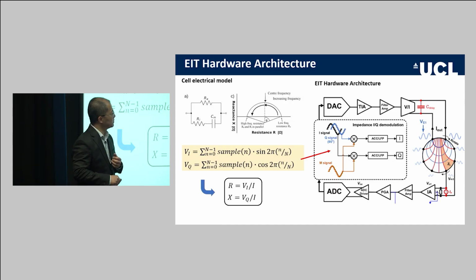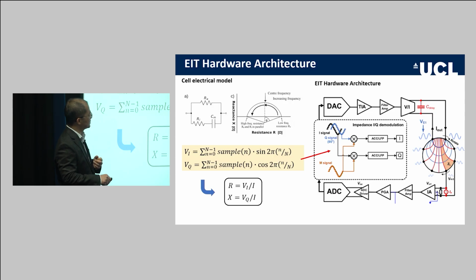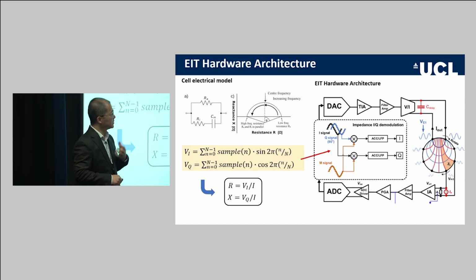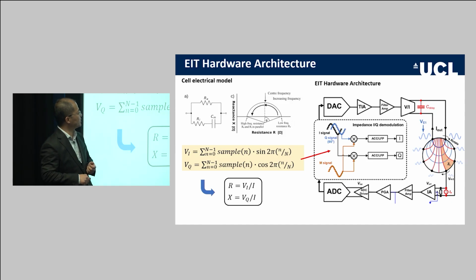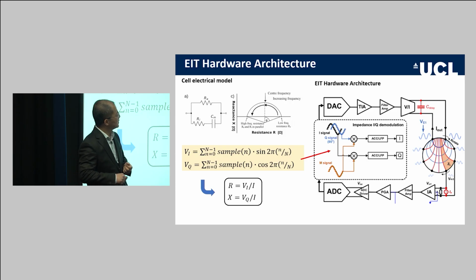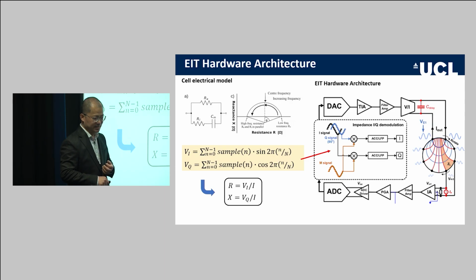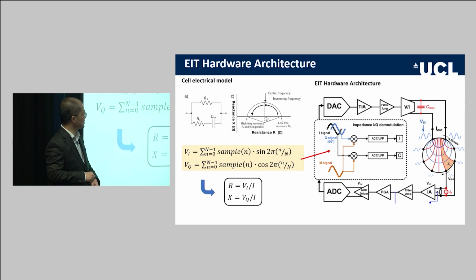So this is a traditional hardware architecture of EIT measurement. We have a sinusoidal wave generator to generate differential sinusoidal current injected to the body, and we measure the voltage response across the electrode array. After conditioning and digitization in the digital domain, we do coherent demodulation. So it's very similar to the principle in communication circuit. We have multiplier to multiply the in-phase and quadrature signal and derive the in-phase and quadrature element after low-pass filtering or accumulation. So the in-phase in this context is resistive and quadrature is reactive. And then we work out the impedance altogether.